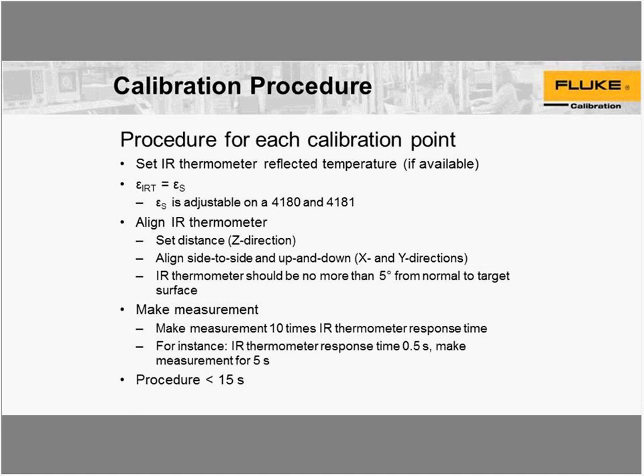At the point you're ready to make the measurement, you should make the measurement for 10 times the IR thermometer response time. For example, both the 4180 and 4181 have a response time of 0.5 seconds. If you use an IR thermometer with a response time of 0.5 seconds, make the measurement for 5 seconds — in other words, 10 times that response time.